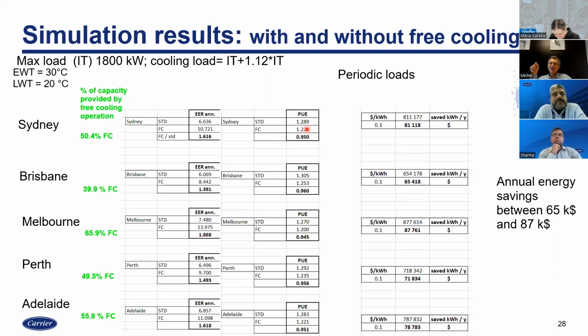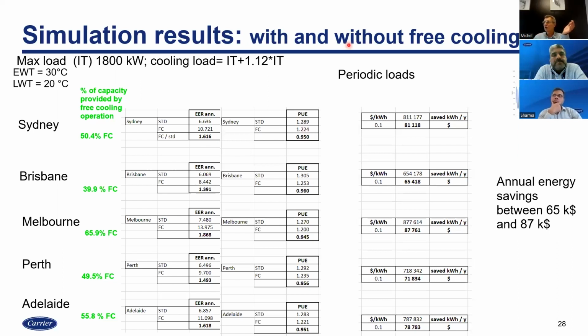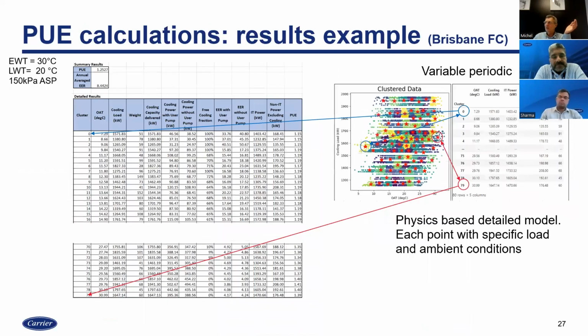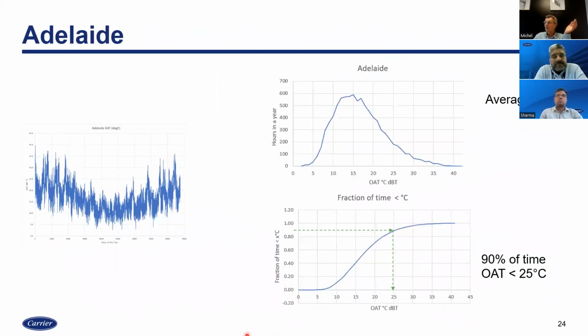I did exactly the same studies 10 years ago for air conditioning applications, and the opposite happened. So I refused to develop the free cooling option for hydronic coils, because we were actually losing more on the air side due to the pressure drop than we were gaining from free cooling operation. This is simply due to water temperature. When you operate with 10°C or 12°C water, looking at your charts relative to the temperatures, if you look at 12°C water, you will have maybe 25-30% of the time when you can get some free cooling, and particularly it happens when air conditioning isn't necessary. So there isn't much gain.